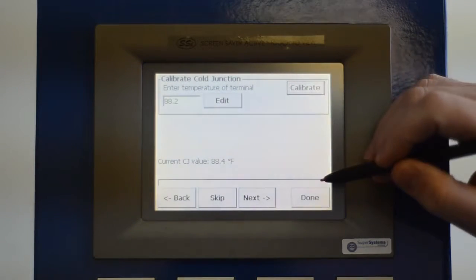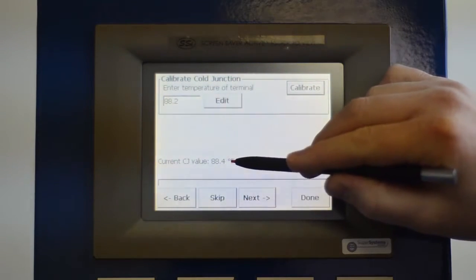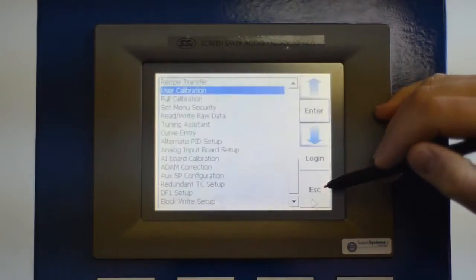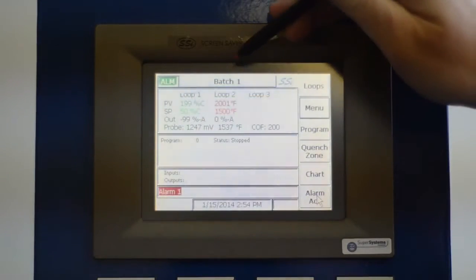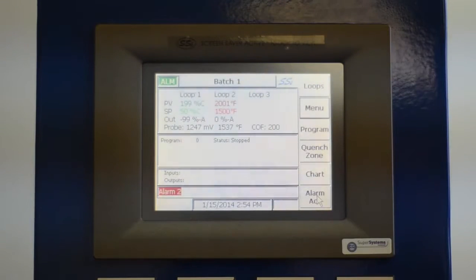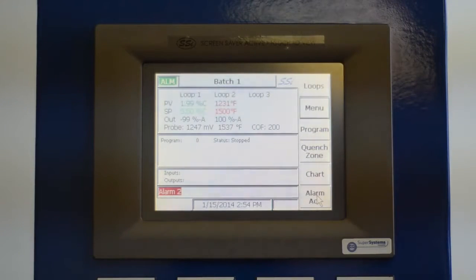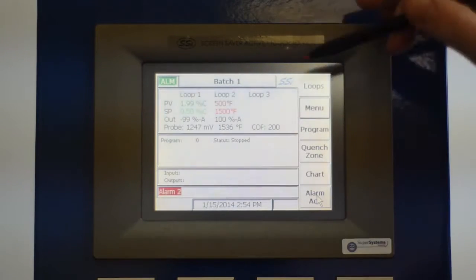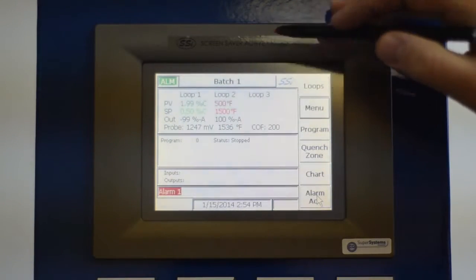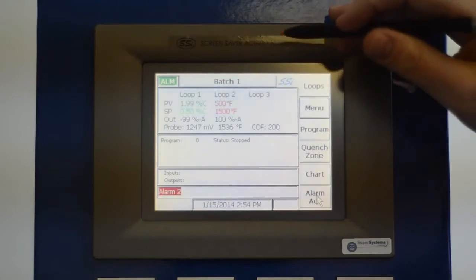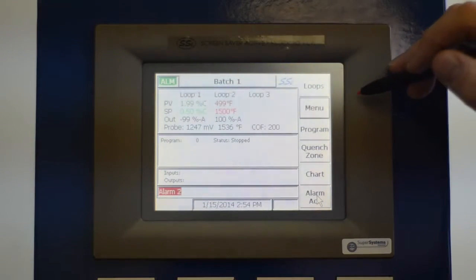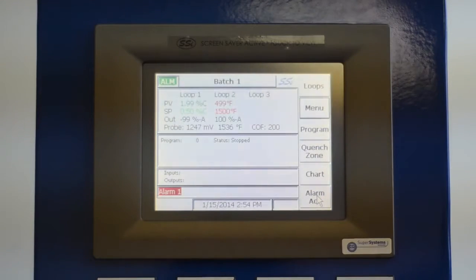Once the procedure is finished, we can then see that the change has been made to the reading. We select done and escape back, and as you can see here, our temperature is changed. I'm going to go ahead and source in 500 degrees. So we didn't change it by very much, 1 degree, so it hasn't made much of a change, or it could be on the edge between 499 and 500. So there you can see it's now reading 499, a degree low.